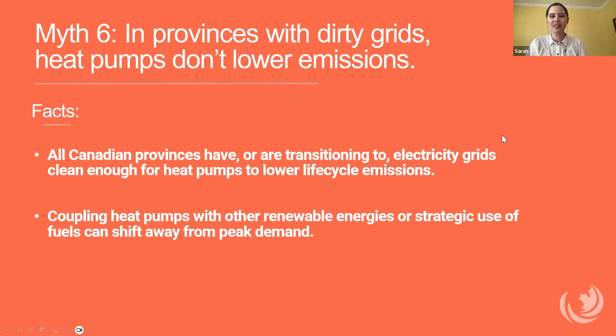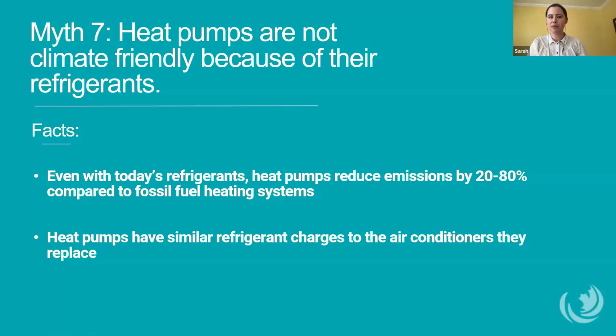So on to myth 7, which is heat pumps are not climate friendly because of their refrigerants. It is true that most heat pumps in Canada use HFC-based refrigerants, which are a potent source of emissions. For example, R-410A, the most popular heat pump refrigerant, has a global warming potential that is about 2,000 times more than that of CO2.